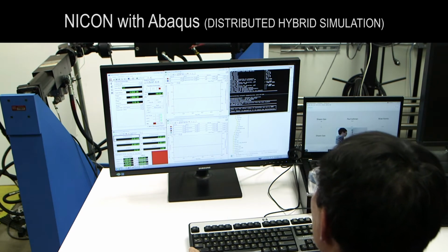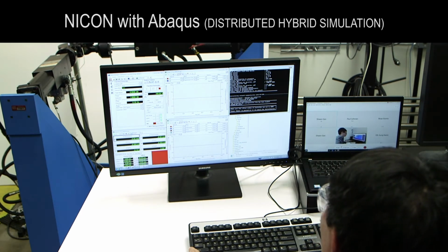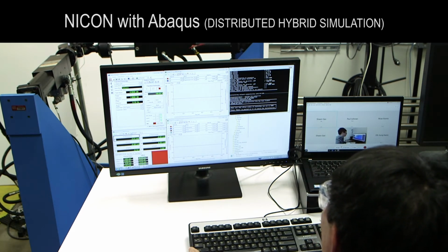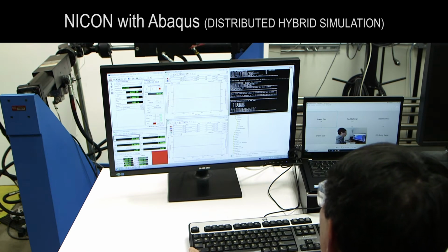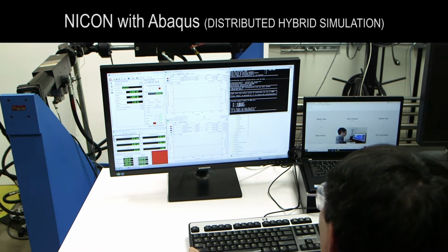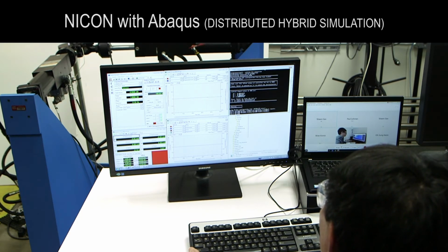Yes, I saw it on my screen here. The connection is being established. So then I can go ahead and let the communication start. And then it does some initial checks on the feedback signals, just to make sure your feedback is not at a large value. Now everything is ready. I'm going to start.